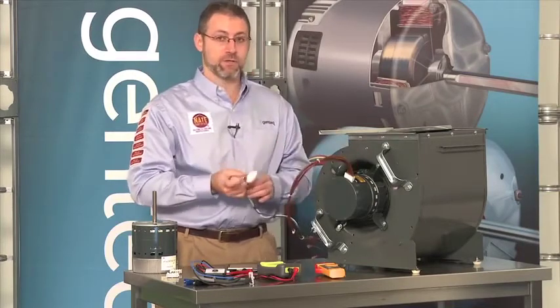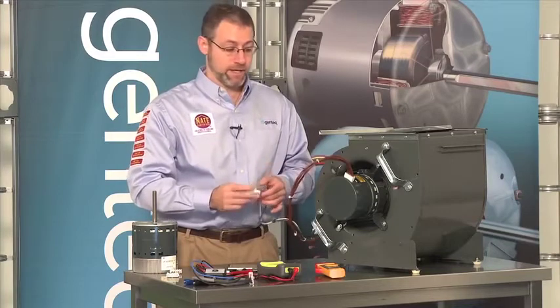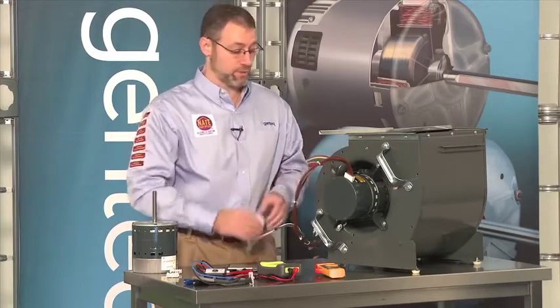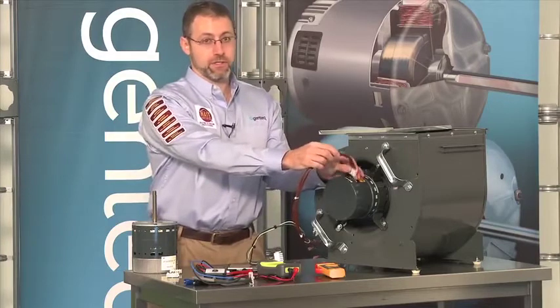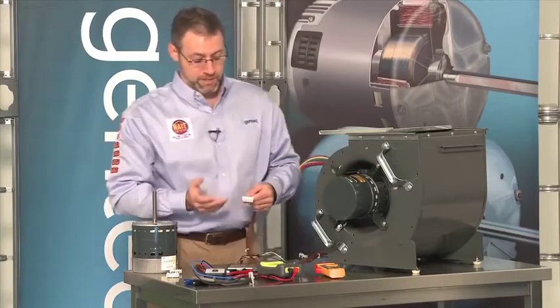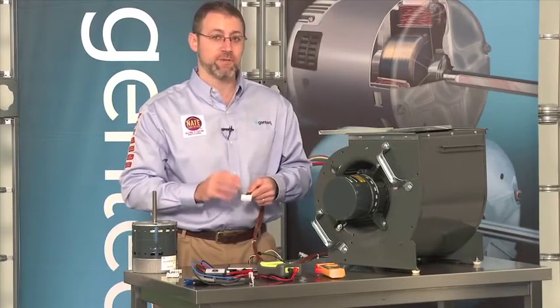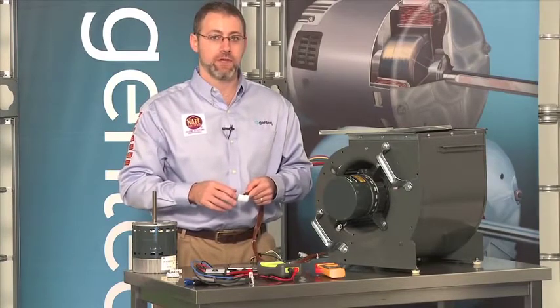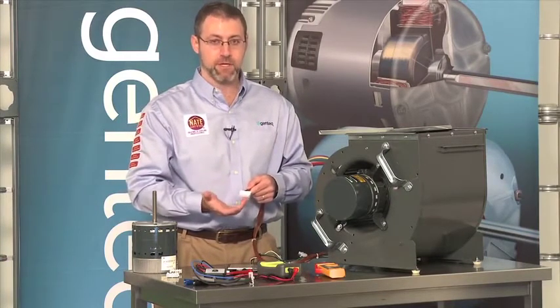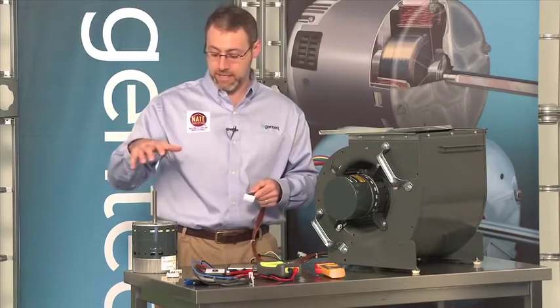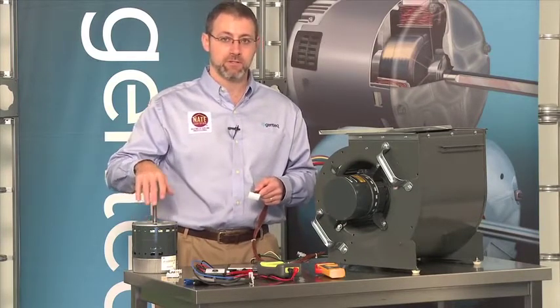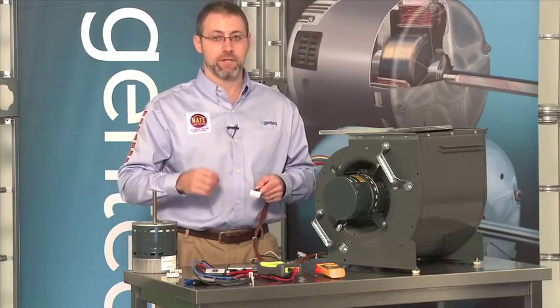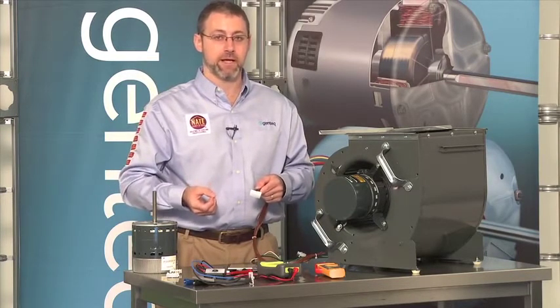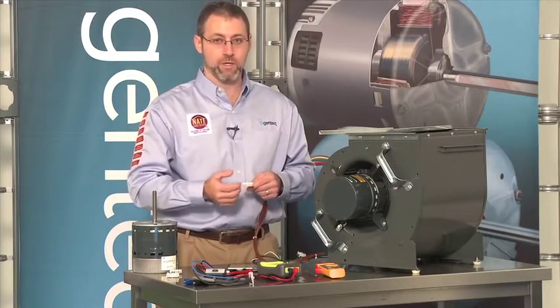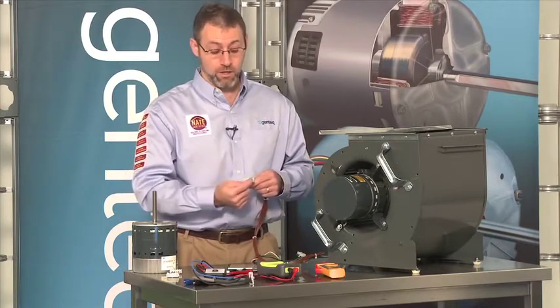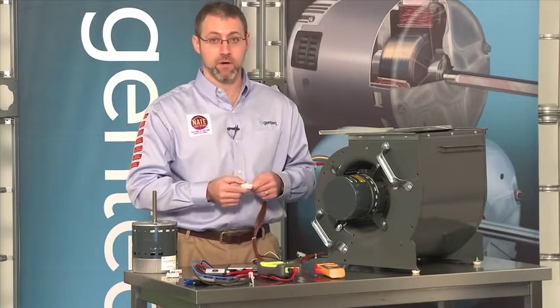Okay? Now let's assume that we already had power there and we think that there may be other problems. So we're going to turn our power off and we're going to disconnect our communication connector. Now the only difficulty in troubleshooting the communication to variable speed motors is that over the years we've used AC communication, DC communication, and in the case of the new 3.0, serial communication. Unless you had the OEM manual for the specific appliance that you're working on, you wouldn't know which type of communication was used or where that communication should be on any of the pins.